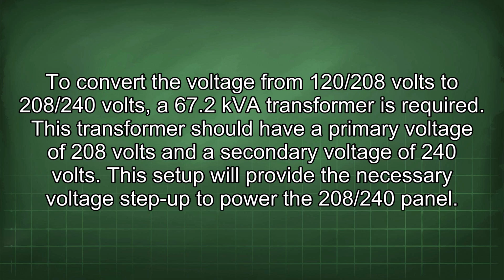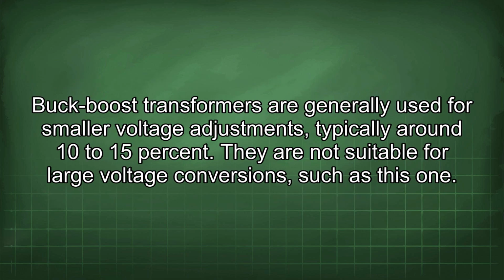To convert the voltage from 120/208 volts to 208/240 volts, a 67.2 kVA transformer is required. This transformer should have a primary voltage of 208 volts and a secondary voltage of 240 volts. This setup will provide the necessary voltage step-up to power the 208/240 panel. Buck-boost transformers are generally used for smaller voltage adjustments, typically around 10 to 15%. They are not suitable for large voltage conversions such as this one.